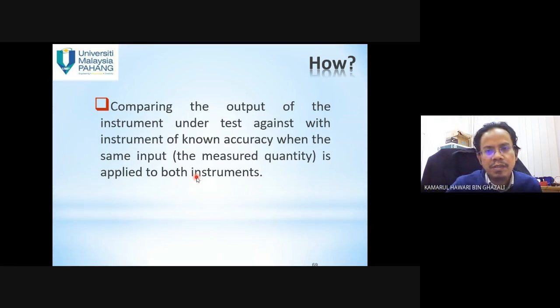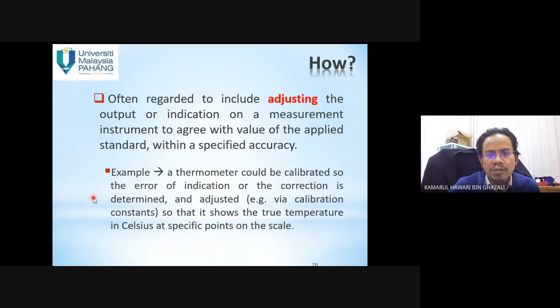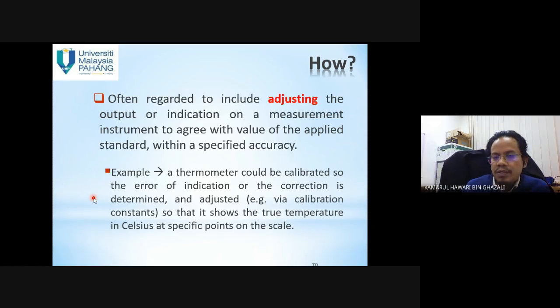Calibration means comparing the output of the instrument under test against an instrument of known accuracy when the same input is applied to both instruments. So this is how we do the calibration. How to do the calibration? It is often regarded to include adjusting the output or indication on a measurement instrument to agree with the value of the applied standard within a specified accuracy. Example, a thermometer could be calibrated so the error of indication or the correction is determined and adjusted so that it shows the true temperature in Celsius at specific points on the scale.